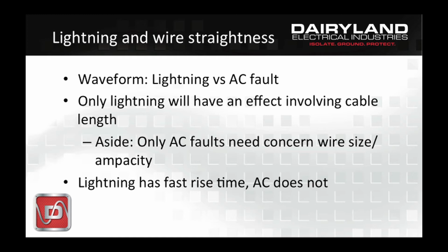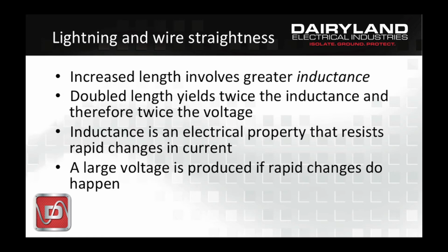Well, the waveform involved that can produce overvoltages could be things like lightning or fault current. But only lightning is going to produce a high voltage that relates to cable length. AC faults, the main concern there is the wire ampacity, the wire size, so that it can withstand the energy of the event. But for lightning, it's all about length. Lightning has a very fast rise time, and AC waveforms do not. And it's this fast rise time that produces the effects that we're concerned about.